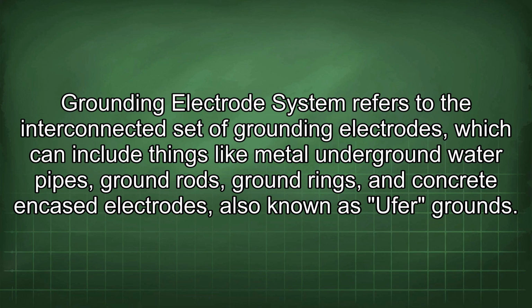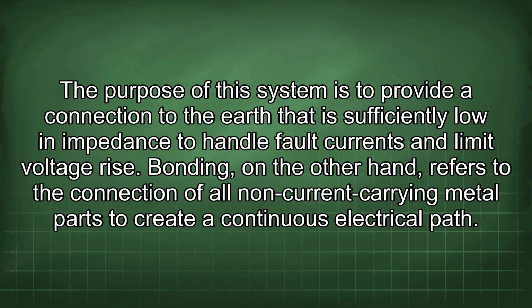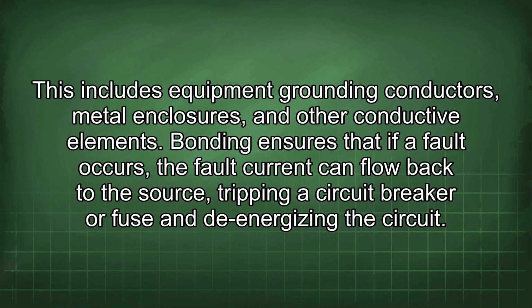Grounding electrode system refers to the interconnected set of grounding electrodes, which can include things like metal underground water pipes, ground rods, ground rings, and concrete encased electrodes, also known as Ufer grounds. The purpose of this system is to provide a connection to the earth that is sufficiently low in impedance to handle fault currents and limit voltage rise. Bonding, on the other hand, refers to the connection of all non-current carrying metal parts to create a continuous electrical path. This includes equipment grounding conductors, metal enclosures, and other conductive elements. Bonding ensures that if a fault occurs, the fault current can flow back to the source, tripping a circuit breaker or fuse and de-energizing the circuit.